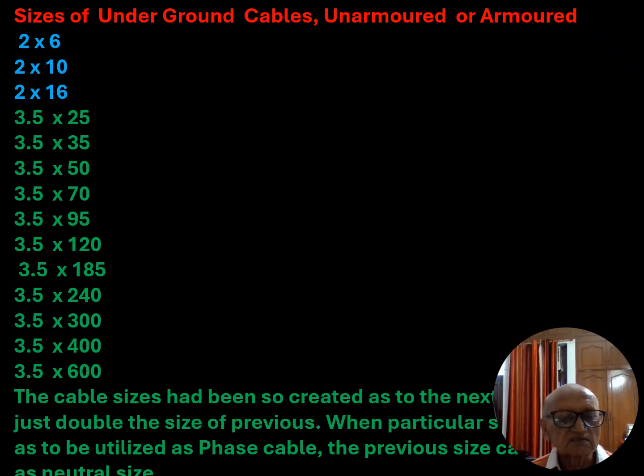Friends, this slide shows the commonly used cable, whether armored or unarmored. Armored in case when it is laid underground, and unarmored when it is laid on the surface or protected places. The first three, 2 into 6, 2 into 10, and 2 into 16 cable, are used for providing submain circuit to SPN DB, which are always prescribed by CPWD.